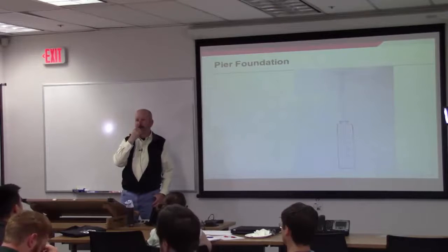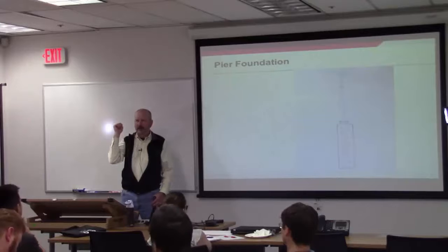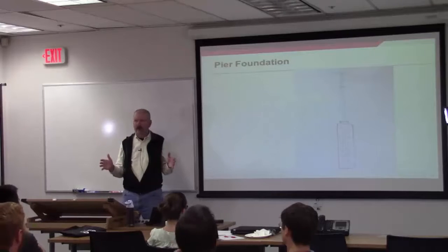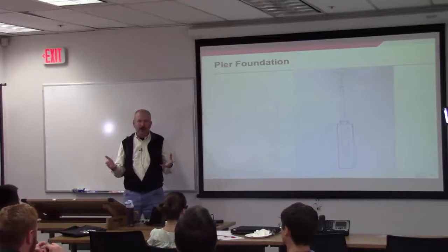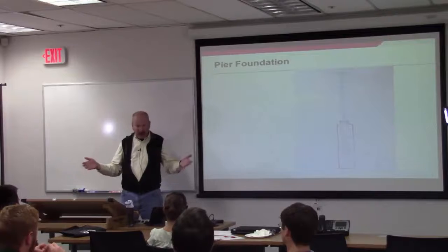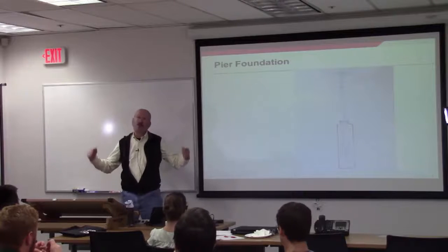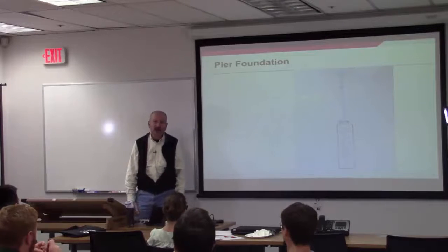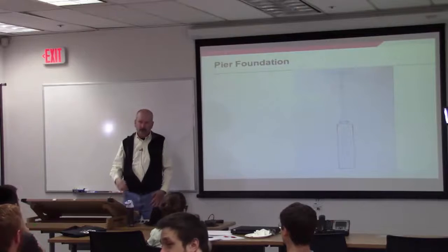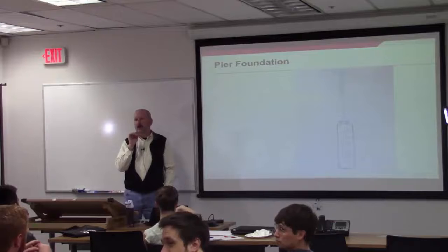I have a really good example of that. Out in The Dalles, we did a project, and some foundations that could have been relatively small because they were founded right on basalt were huge, and they said, why did you design them so big? And we said, well, why didn't you give us a soils report so we knew that this was down here? Yeah, and it's a real problem, and nobody wants to pay the geotech to do it.